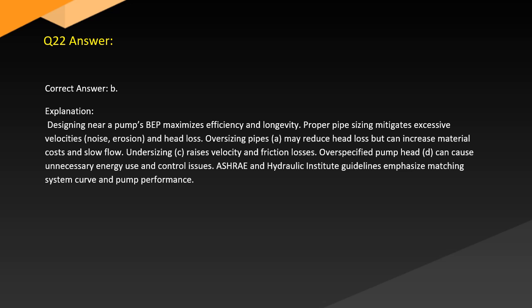Designing near a pump's BEP maximizes efficiency and longevity. Proper pipe sizing mitigates excessive velocities, noise, erosion, and head loss. Oversizing pipes, A, may reduce head loss but can increase material costs and slow flow. Undersizing, C, raises velocity and friction losses. Overspecified pump head, D, can cause unnecessary energy use and control issues. ASHRAE and Hydraulic Institute guidelines emphasize matching system curve and pump performance.